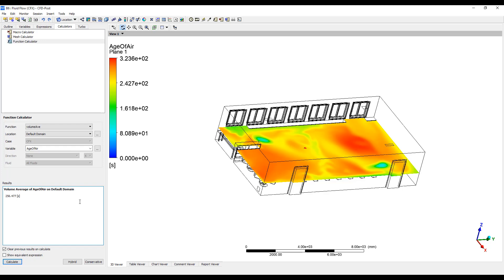So, this tells you a quick way of calculating and doing a simulation. The setup is pretty simple. This mesh is probably quite a bit more dense than it needed to be, but the results are the same. We're able to calculate the mean age of air inside this room at any location.